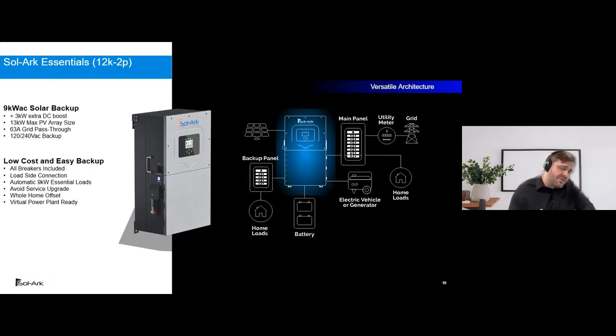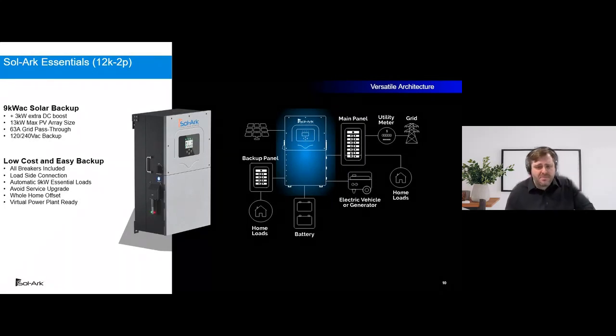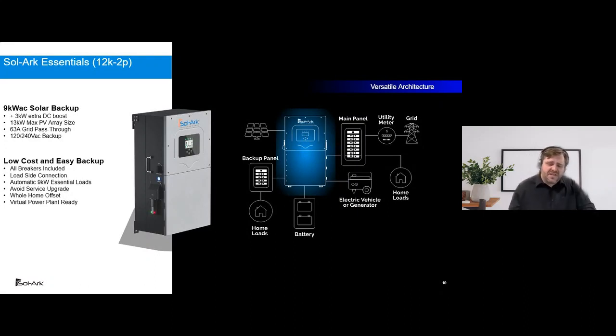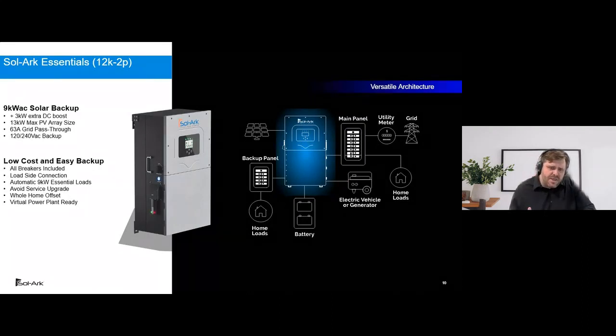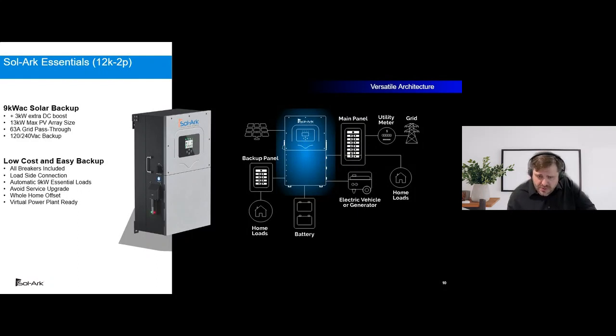Now, why would you go with the 12K instead of spending a little bit more to go with the 15K? Well, the first answer is most customers go with the 15K. However, the 12K does have some advantages. First, it includes all of the breakers. So it has a solar, grid, generator and battery breaker, whereas the 15K you have to bring your external grid disconnect and your generator disconnect.